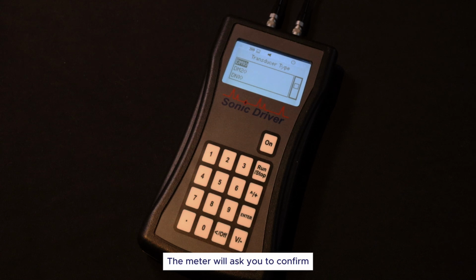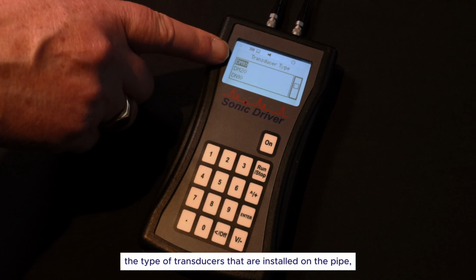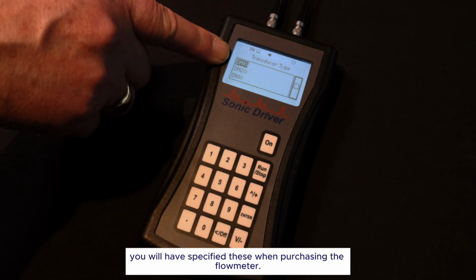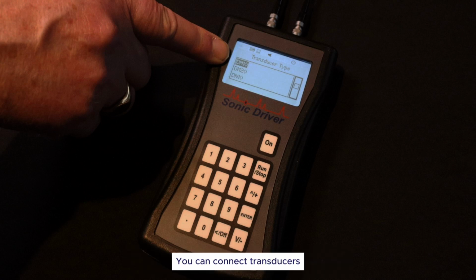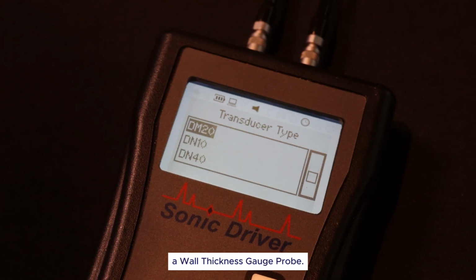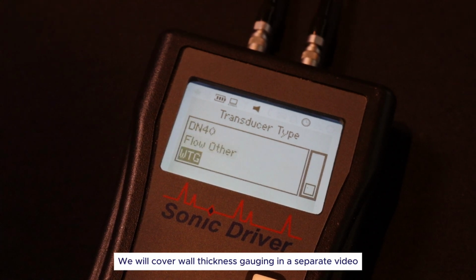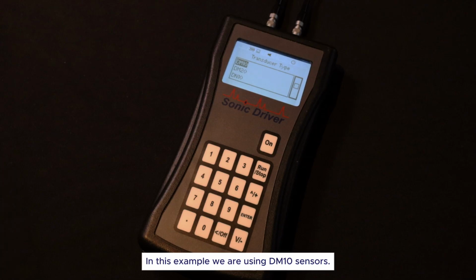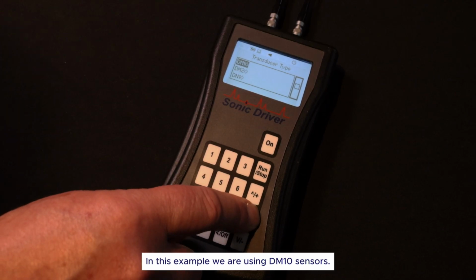The meter will ask you to confirm the type of transducers that are installed on the pipe. You will have specified these when purchasing the flow meter. You can connect transducers operating at different frequencies, and if you have one, a wall thickness gauge probe. We will cover wall thickness gauging in a separate video, but the functionality is included as standard. In this example, we are using DM10 sensors.